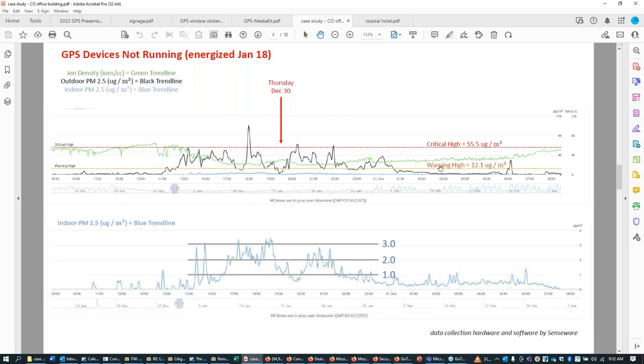The EPA says that for PM 2.5, if you exceed 12 micrograms per cubic meter, then you're no longer considered in the healthy level. And if you get to 55, it really becomes pretty seriously unhealthy. What we captured on the building data was that we had an outside air excursion that lasted for several hours on Thursday, December 30th. And this black trend line shows that we went above 12 for several hours. We exceeded 55 for a brief amount of time.